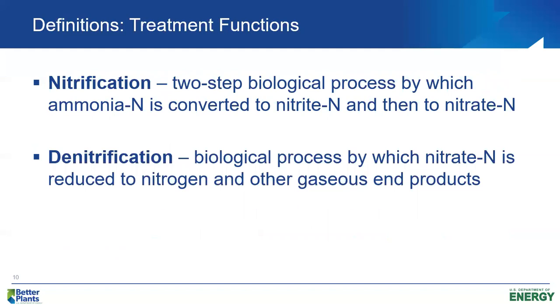Nitrification, we talked a little bit about it in our first presentation. Again, it's a two-step process. In the first step, ammonia nitrogen is oxidized to nitrite nitrogen, which is NO2 nitrogen. The bacteria that do that are called the ammonia oxidizing bacteria. The second reaction is the oxidation of nitrite nitrogen to nitrate nitrogen. Nitrate is NO3 nitrogen. The bacteria that achieve that for us are the nitrite oxidizing bacteria.